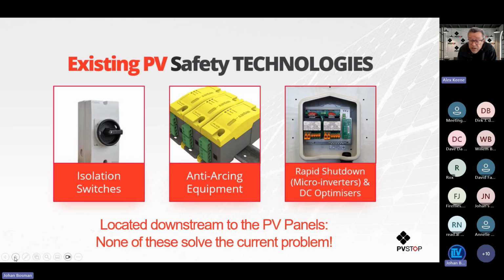Rapid shutdown microinverters and DC optimizers are excellent pieces of kit, designed specifically to help. But there are question marks over their fireproof rating — how do they react when an external event is compromising the PV system? Or the rapid shutdown system itself could be an area where a compromise or connection failure could occur.